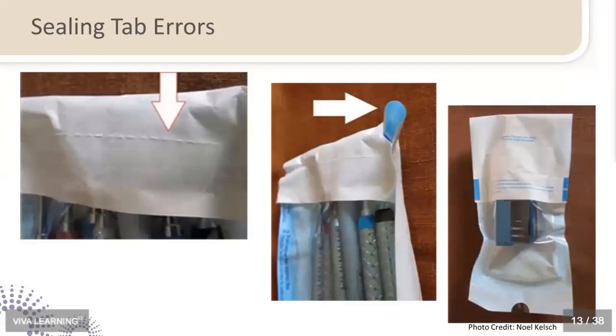This is talking about that perforation that we addressed earlier on, and you can see sometimes, you know, we all get in a hurry, and we are wearing our heavy-duty chemical puncture resistant utility gloves when we're packaging instruments. And so sometimes it's a little bit unwieldy, and we need to make sure that we are following the instructions for how those pouches are to be sealed, because again, it has to do with the integrity of the seal and the ability to maintain that sterility long term. So what I suggest to people is, before you put the first instrument in that pouch, fold the flap over and then run your index finger and thumb along that perforation. It creates a memory seal so that once you have the instruments in and that pouch is now bulked up a little bit, that flap almost knows exactly where it's supposed to be placed for complete closure.